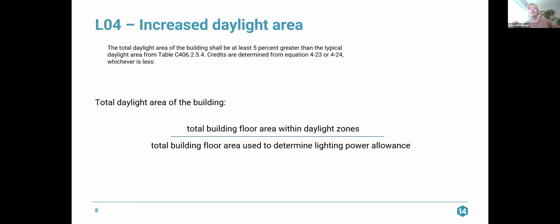The total daylight area of the building is going to equal the total building floor area within daylight zones divided by the total building floor area used to determine the lighting power allowance. So you're not necessarily looking at the gross floor area. I was trying to think about an area of the building that wouldn't have lights. And the only thing I could think of was like a mechanical shaft. Or you probably have lights in elevator shafts.